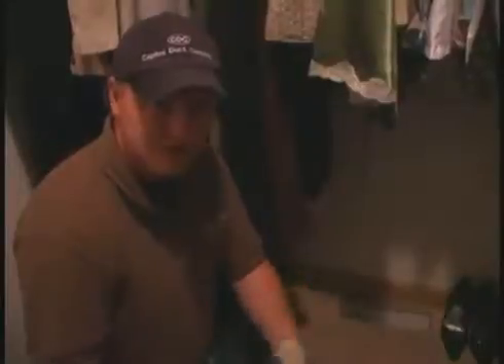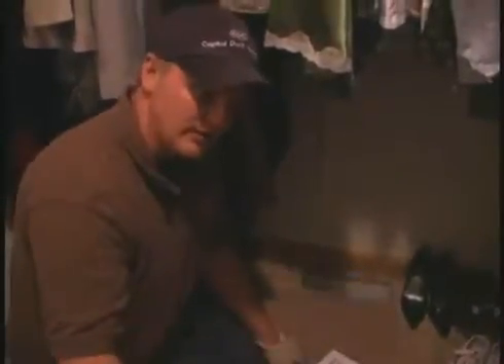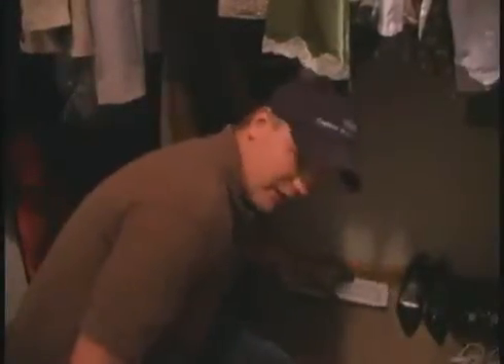You don't have a fixed brush of just 4 inches or 6 inches, because a lot of times when you go inside a duct system, it'll go from the 6-inch into a Y, which turns into an 8-inch. And so a lot of times the 6-inch brush won't get into that. Normal brushes get into the corners of a trunk line because trunk lines are square, and when they're spinning, they like to go into one corner of the trunk line. Other than that, they can't really do much more.